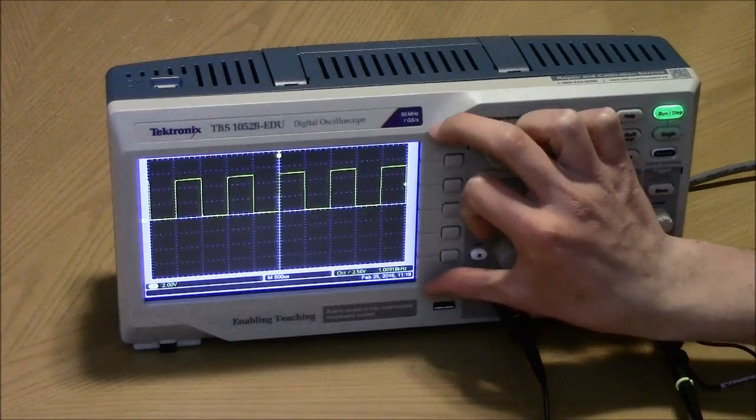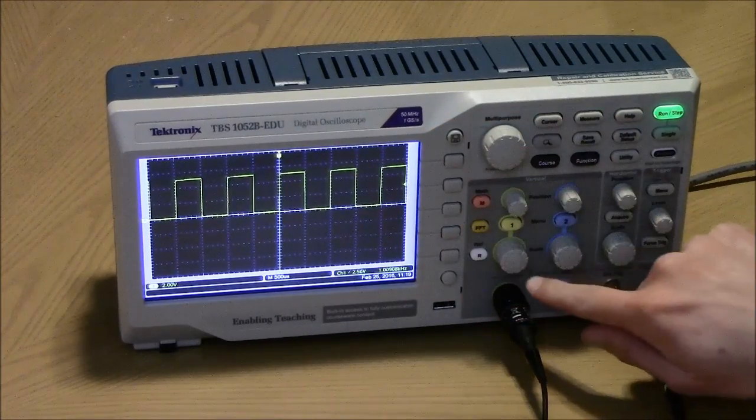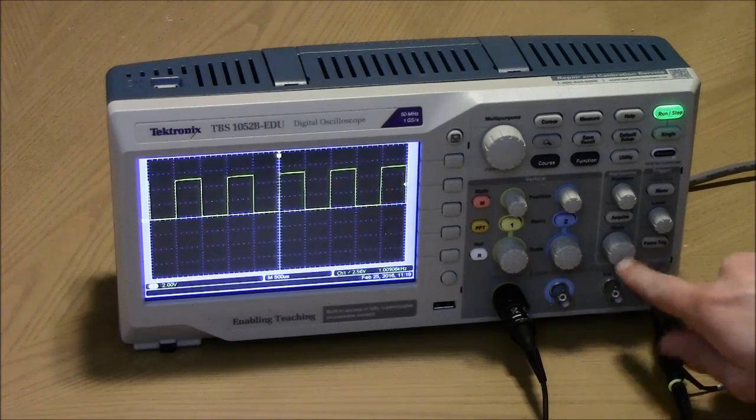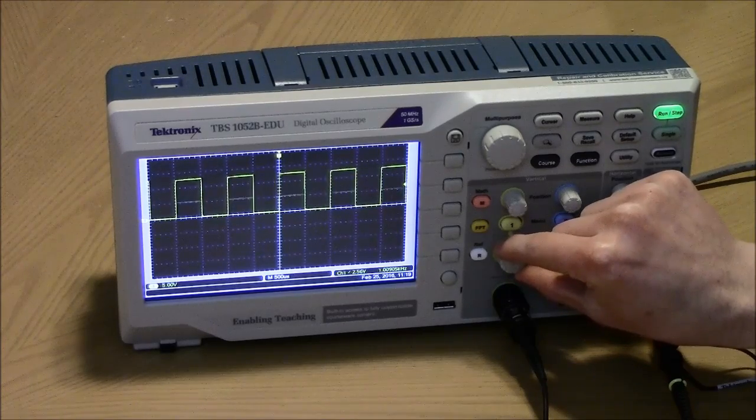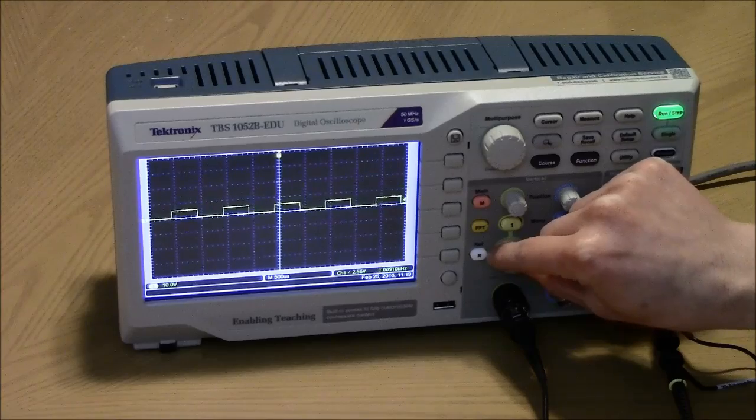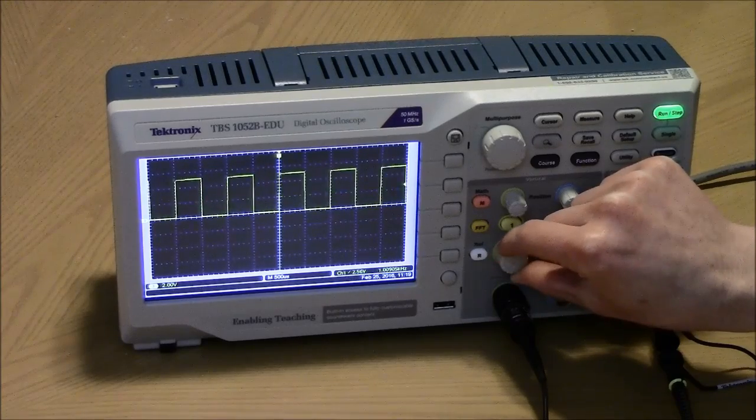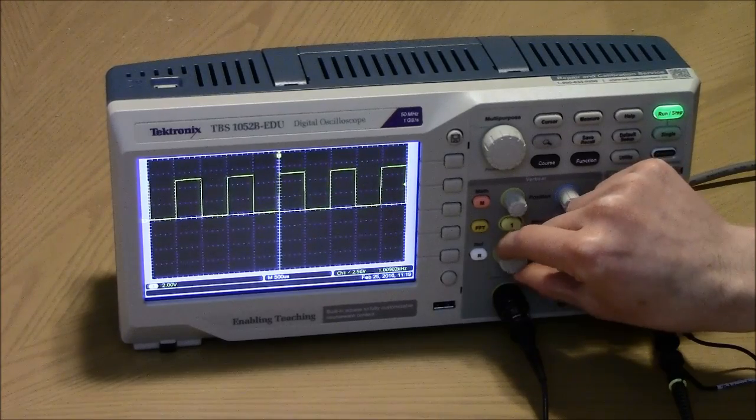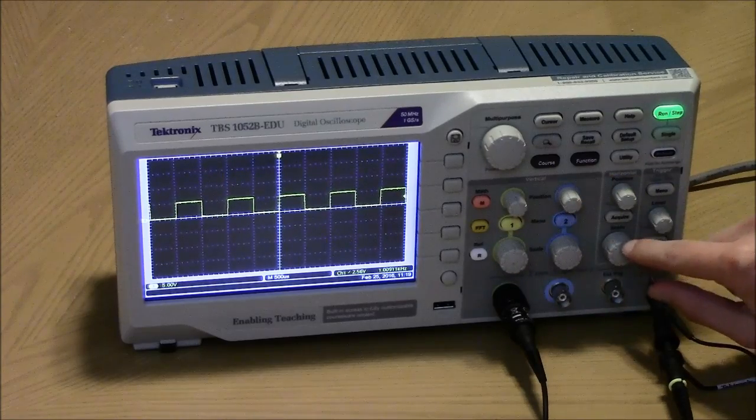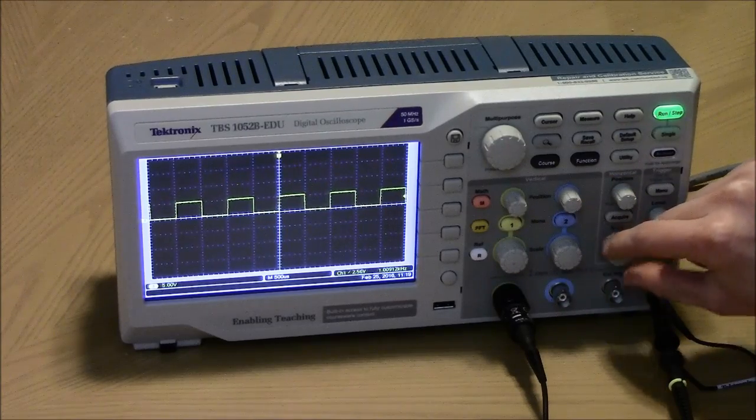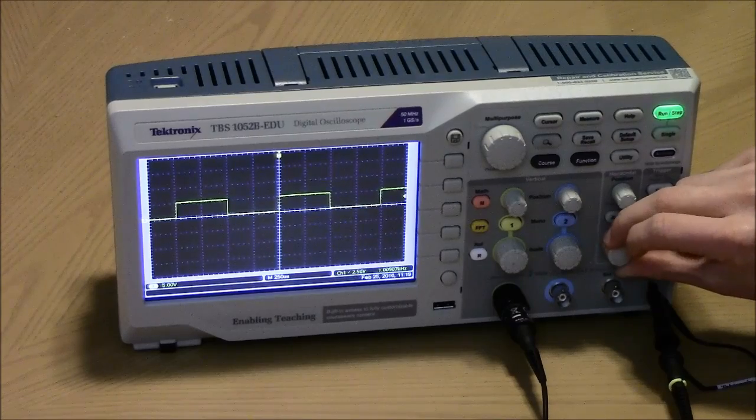You can change the scale that you view here with this dial and this dial. This dial changes the height sensitivity. And this dial changes the width that you see.